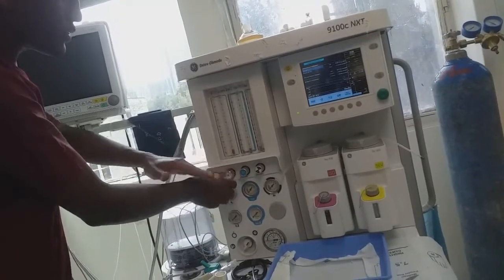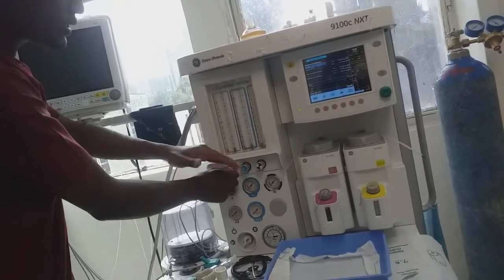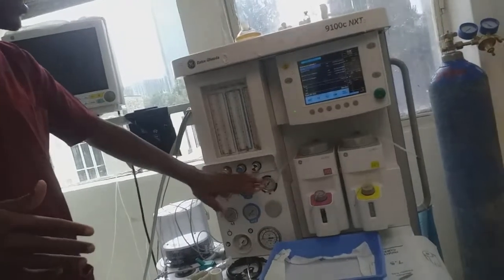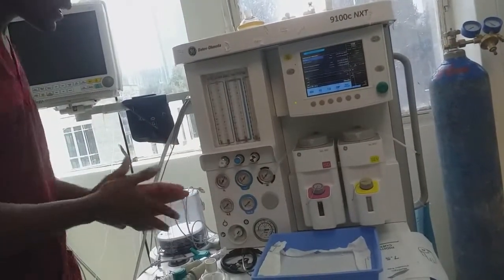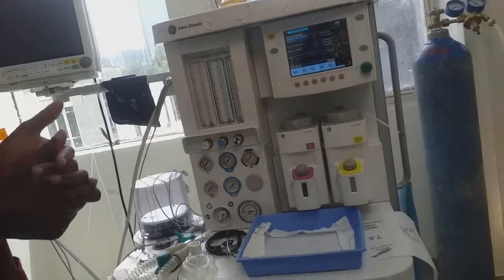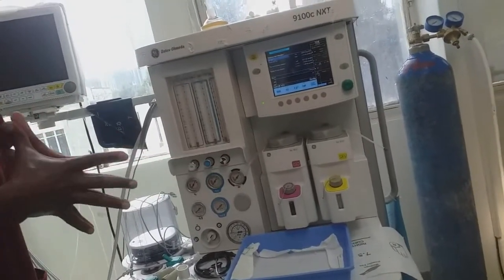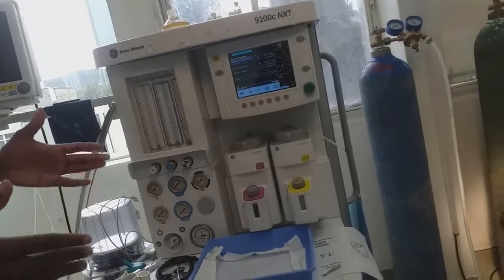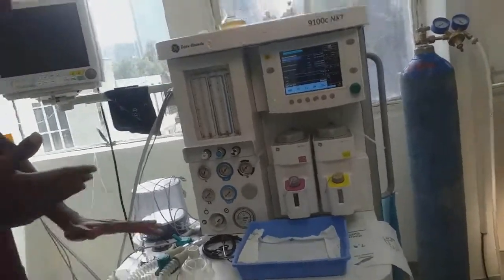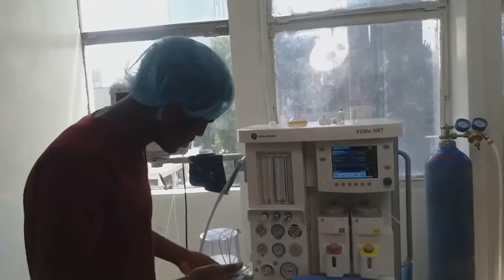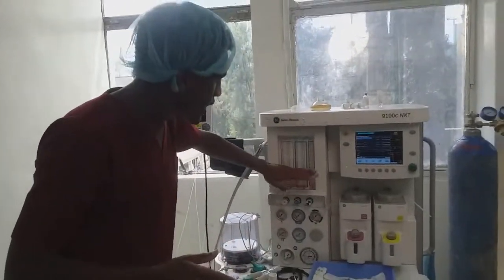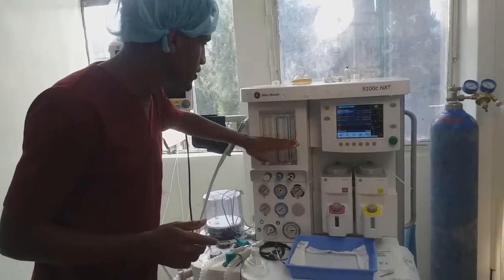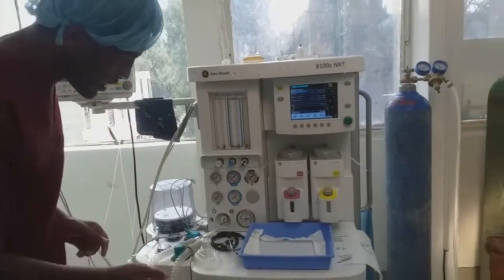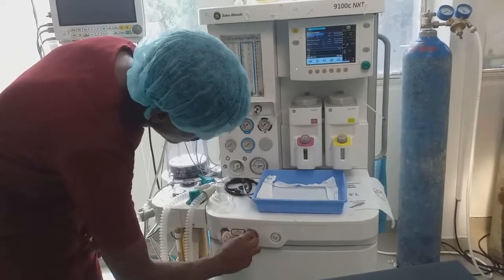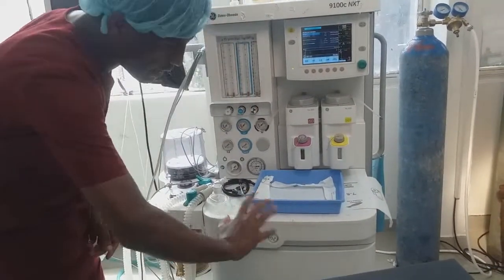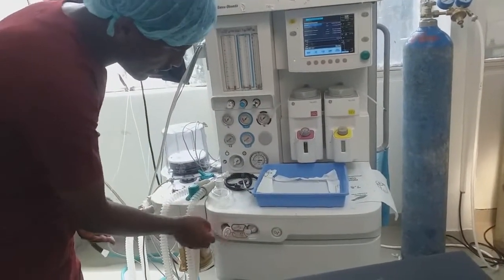If we close only the oxygen cylinder, the nitrous oxide control knob should be closed. This anti-hypoxic device is one indication in our anesthesia machine check. To check for any leak from the flow meters, I have to switch this to the common gas outlet. I have to change it.